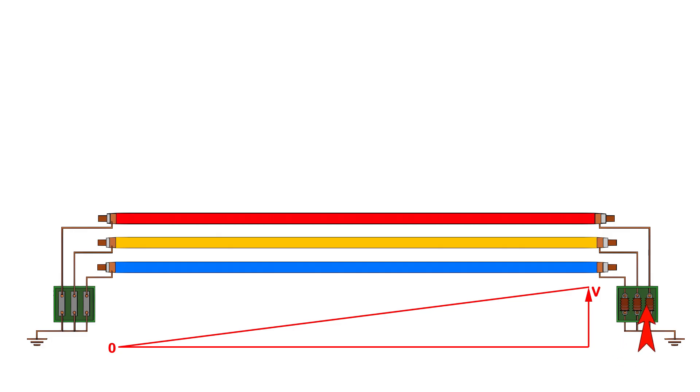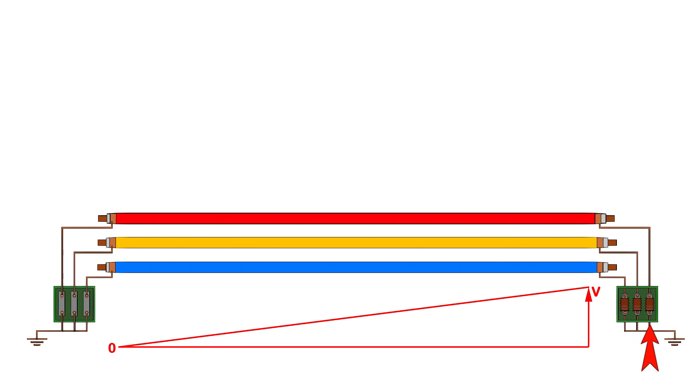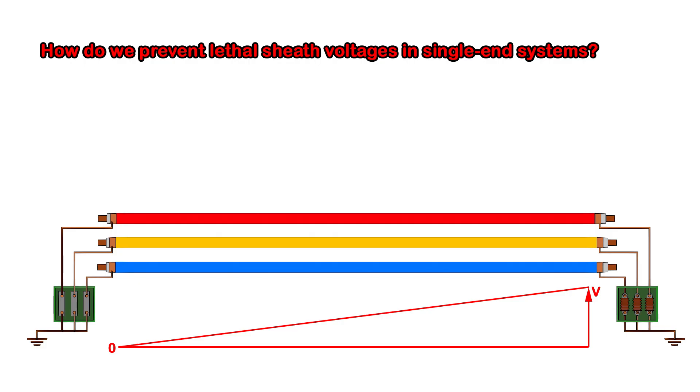These are sheath voltage limiters. Therefore, these ends are not directly connected to the earth. So, how do we prevent lethal sheath voltages in single-end systems? The answer lies in combining sheath voltage limiters with an earth continuity conductor.